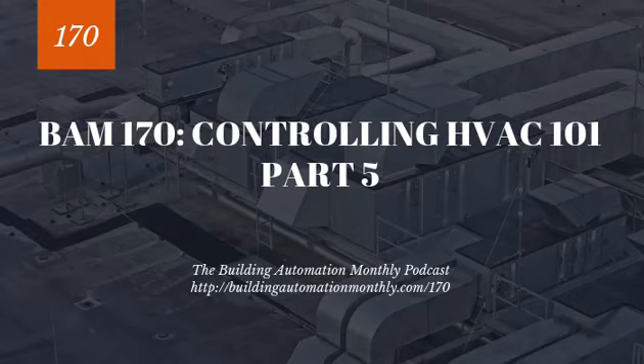Now we're going to go a lot deeper into primary secondaries. We're going to go a lot deeper into decouplers in just a second, but I want to talk about one last thing, which is DeltaT at full load conditions. So you have a coil and it's designed with a 10-degree delta, right? But due to it being plugged or whatever, you're only getting an 8-degree delta. And so this means running at full load, we are only using 80% of its load. And this perceived lack of load is going to cause the secondary pumps to run harder. We're going to turn up, potentially going and staging additional chillers.